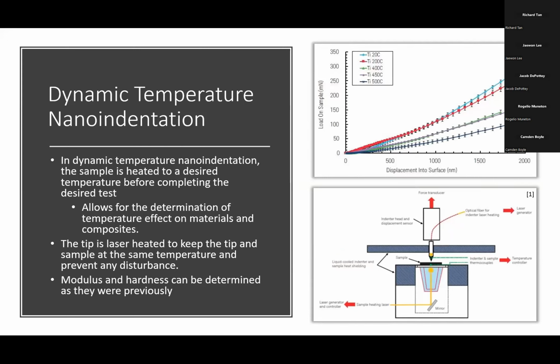So you can also do these nano indentation tests with dynamic temperature, in which the sample is heated to a desired temperature before you do these tests, and the tip that is being used is also heated up to the same temperature. And these tests allow you to determine temperature effects on materials and composites. So if you look here to the right, you can see there's a diagram. The lower right image is a diagram of how you might heat up your sample and your tip. So you have a laser that is hitting a mirror at a 45-degree angle to reflect onto the sample to heat it up, with an optical fiber in the tip to heat it up to an equal temperature.